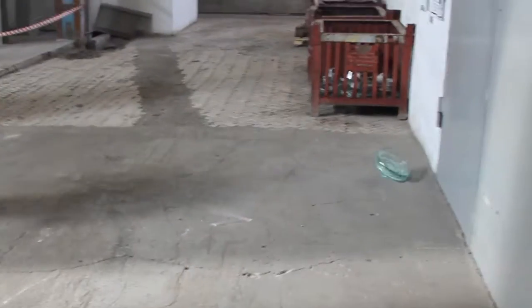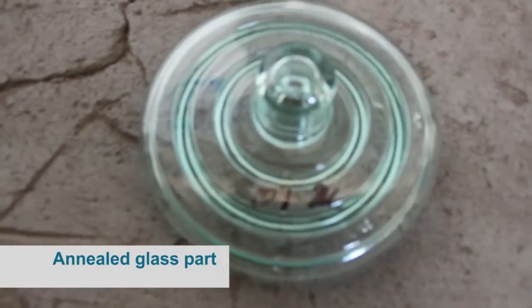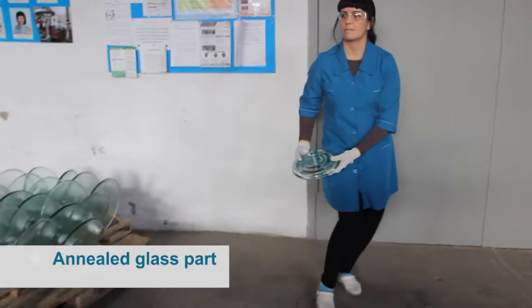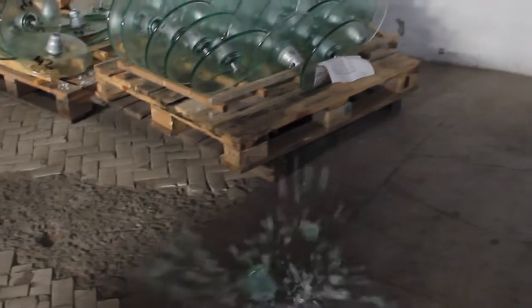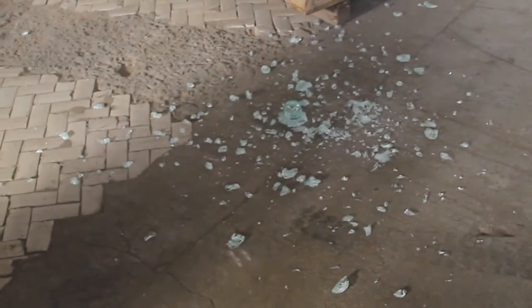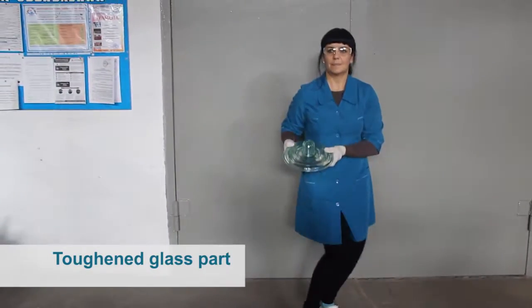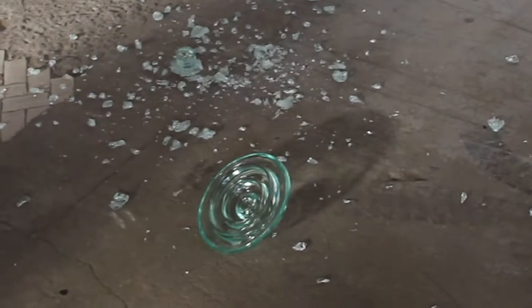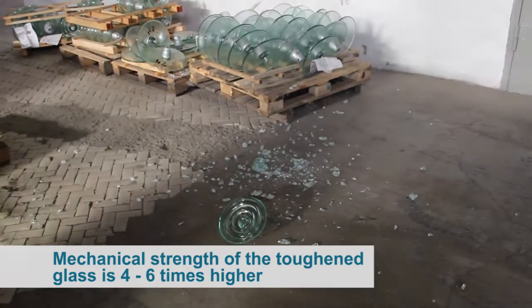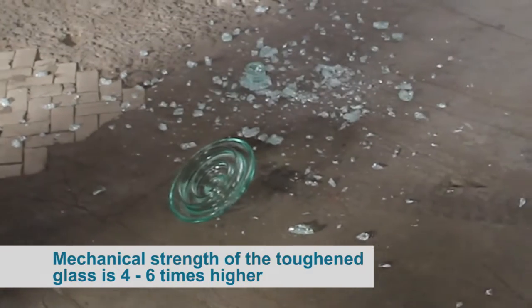Let's conduct the same experiment with the annealed glass part. We throw it on a cement floor. Have a look. It is broken in flinders. The same occurs both during transportation and installation, and under strong mechanical impact. Thus, mechanical strength of toughened glass is 4 to 6 times higher than annealed glass and other insulating materials.